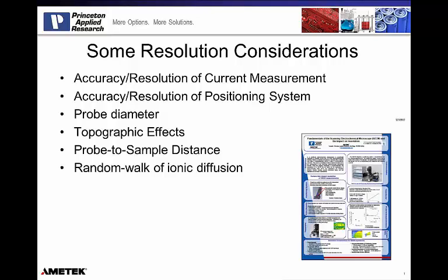So let's walk through this a little bit further. Then topographic effects we've touched on a couple of times today, and that is if you have tilt or complex geometry of your sample surface, it's going to convolute, or it's going to have two different parameters influencing the current measured at the probe. Then we're going to look down and we're going to see probe to sample distance as an impact. This is quantified by our approach curves. The closer you get to the sample surface, the better that ratio of current over the conductor and current over the insulator becomes a higher value. So really that electrochemical sensitivity becomes higher.